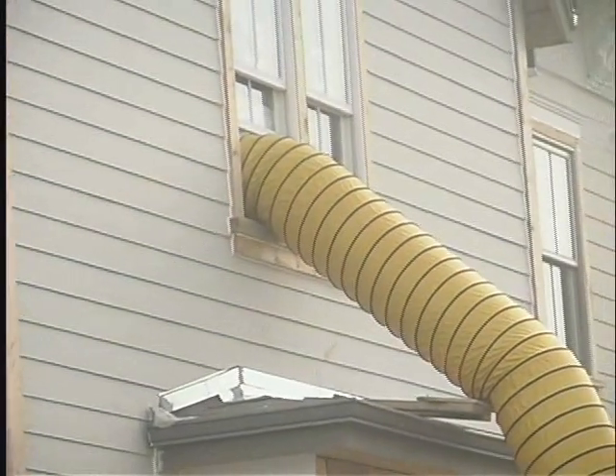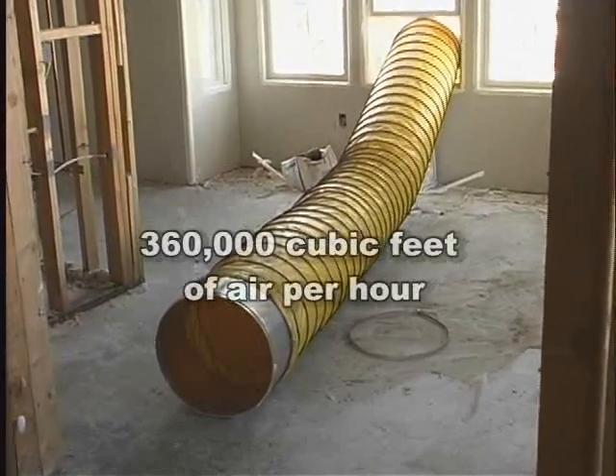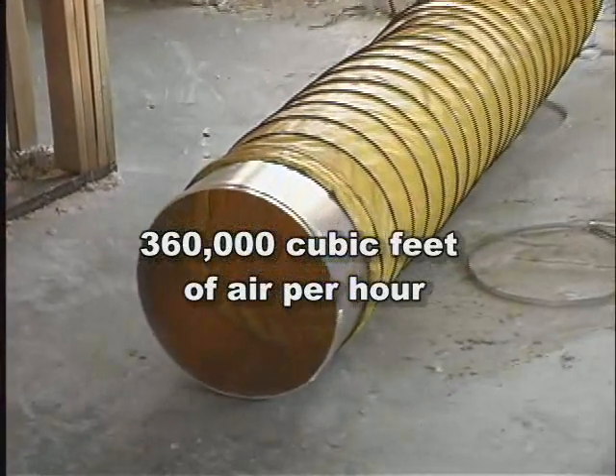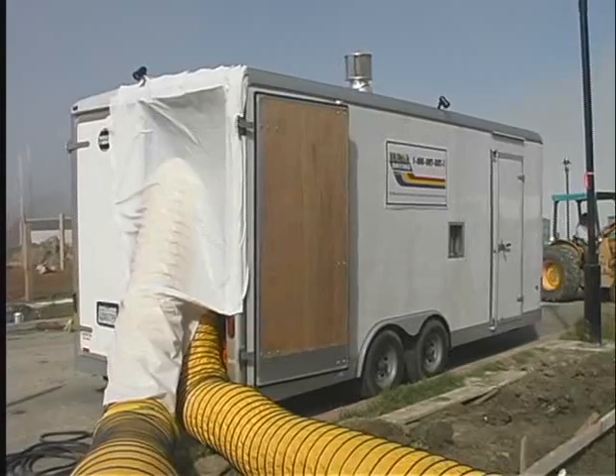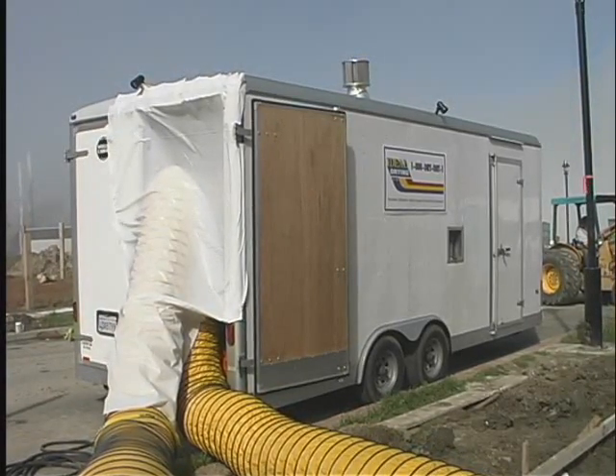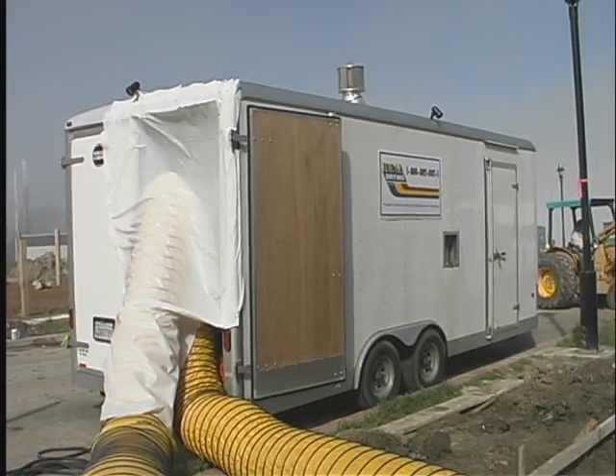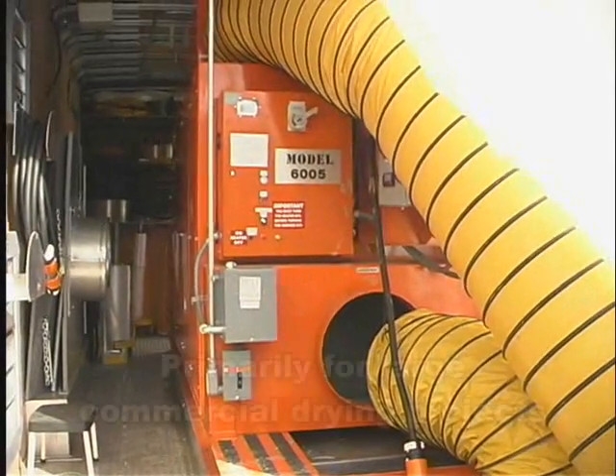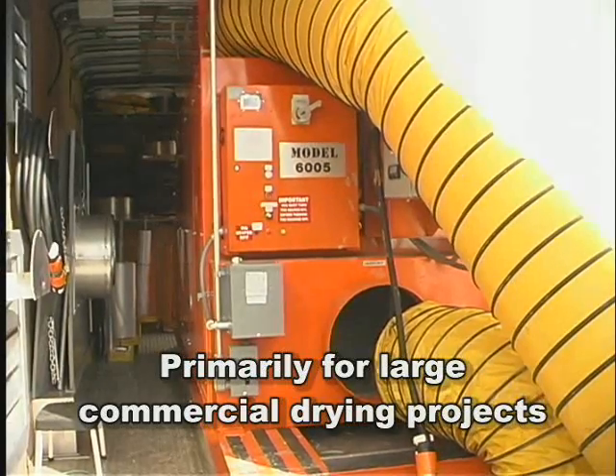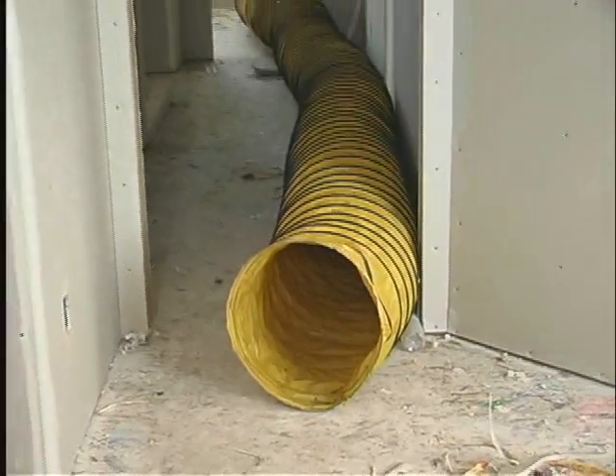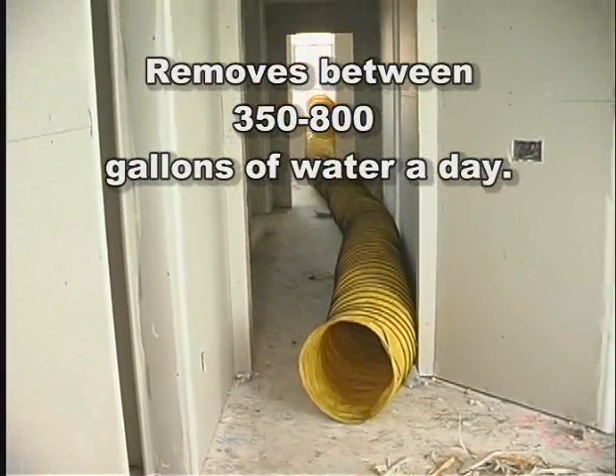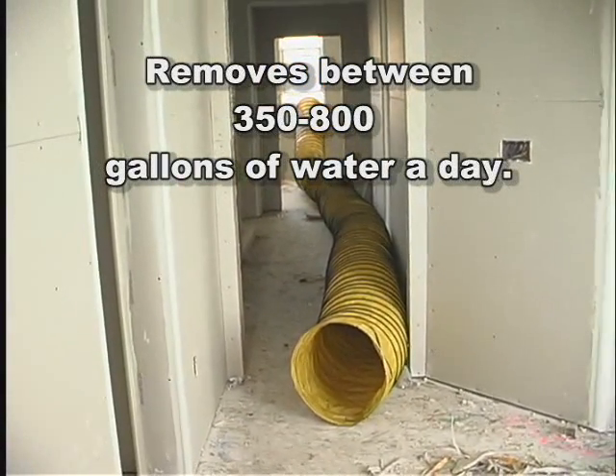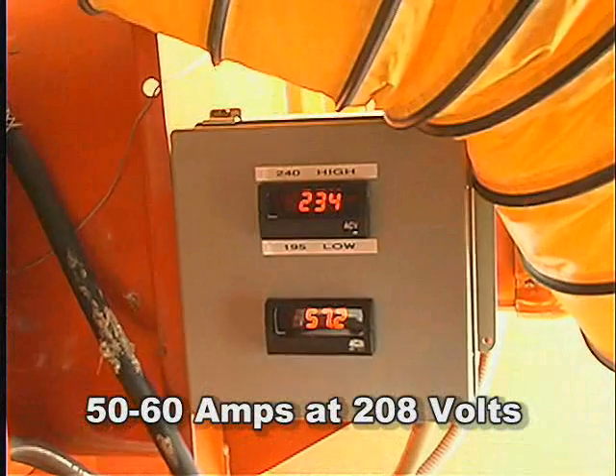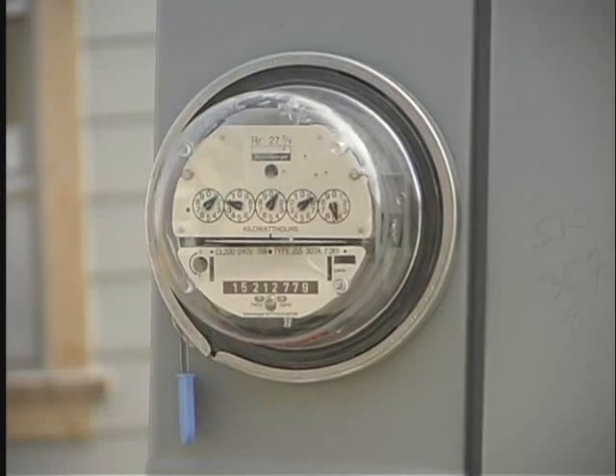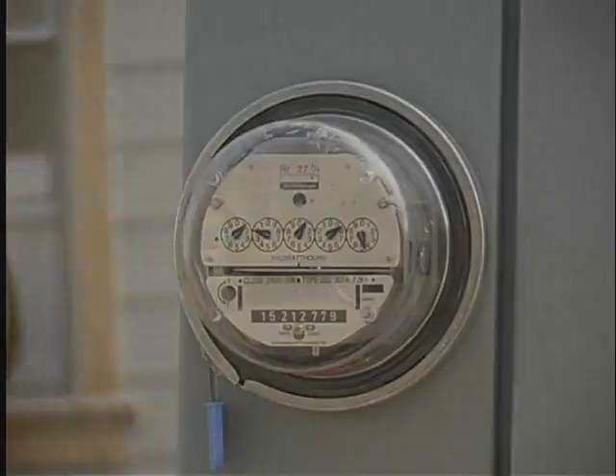The 6,000 CFM mobile desiccant dryer can process up to 360,000 cubic feet of air per hour. With the use of this machine, it is not necessary to have a portable generator unless there is no electrical supply in the building. The 6,000 desiccant is designed primarily for large commercial drying projects. Operating under constant heavy humidity conditions, this machine can remove between 350 and 800 gallons of water a day. The machine will draw 50 to 60 amps and 208 volts, which can be made available through a licensed electrician attaching the wires directly to the main electrical panel with a breaker of most buildings.